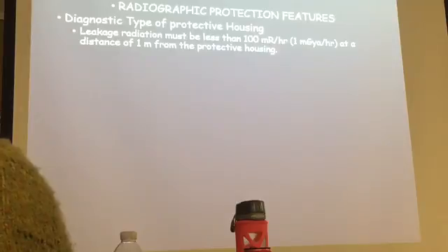On the other hand, from experience, from equipment that I've seen and how equipment is tested, hardly ever do you even come close to this. Manufacturers don't take a chance. They are not going to go cheap on this, because if they do, the FDA, remember, the FDA is the entity in charge of X-ray equipment and the manufacturing licensing of X-ray equipment. Do you remember that? Okay, good. They are not going to allow them to sell their equipment in the U.S. This is the largest market in the world. They are not going to take a chance. And so equipment doesn't even come close to that.